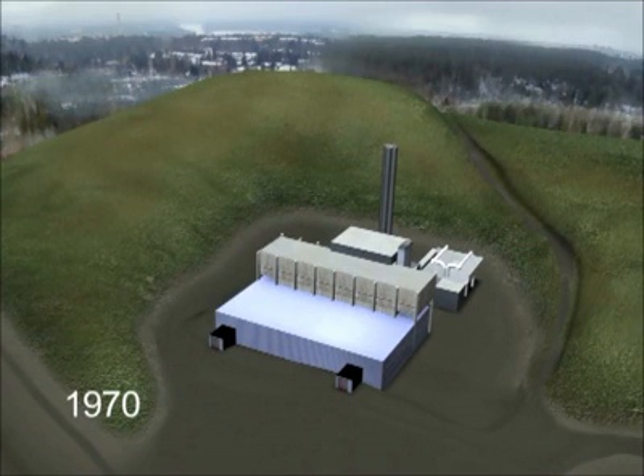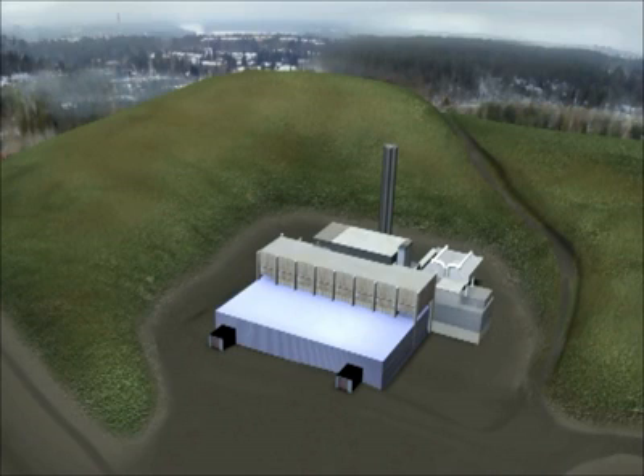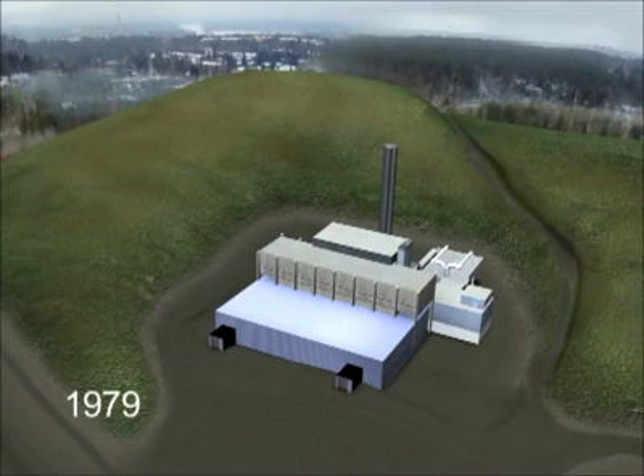Even then the works was a modern workplace with the latest technology. Flue gas purification using electrical filters and energy recycling in the form of electricity production with the aid of a turbine. In 1979 the heat and power plant was connected to Farsta district heating systems. In connection with this, a liquid fuel boiler producing 80 megawatts and 2 20 megawatt hot water boilers were built to handle high load periods in the network. Heating needs in the region grew and 3 years later an electric boiler was installed.